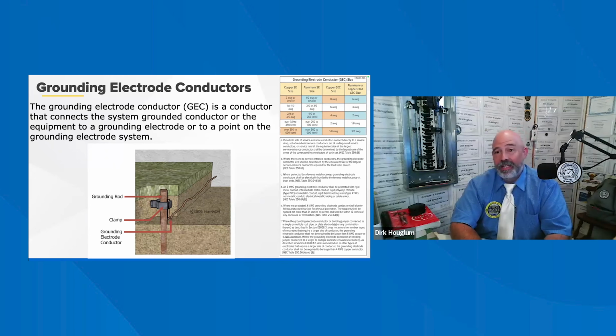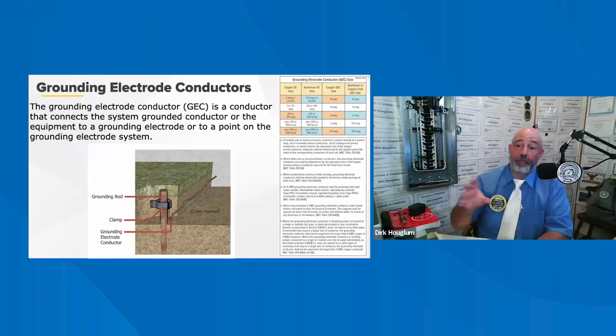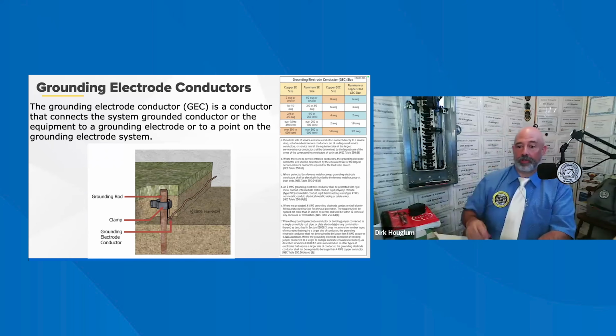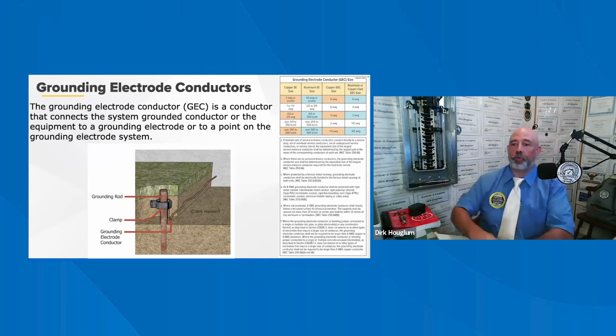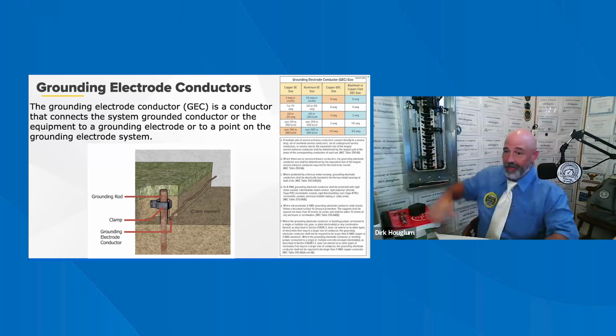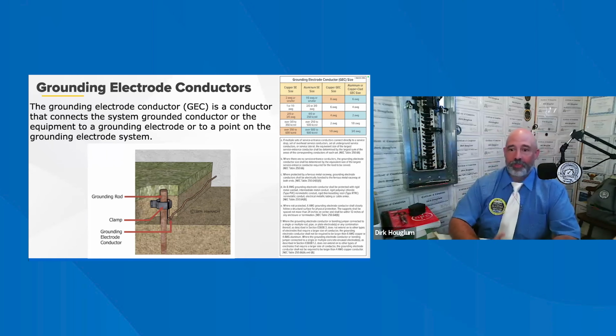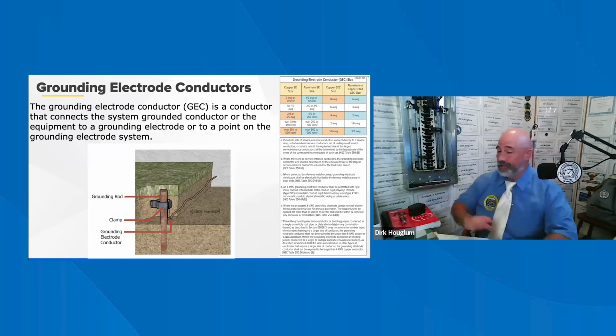Remember, the GEC should be connected only to the neutral and the service panel, the panel containing the service disconnect, and nowhere else. The GEC is usually connected to the grounded service conductor, the neutral service conductor, in the service equipment where the main disconnect is located or in the meter enclosure. The grounding electrode conductor, the GEC, and the grounded service conductor are bonded together to the metal enclosure by the main bonding jumper, screw, or jumping connector in the neutral bus bar. That's what this does, okay?